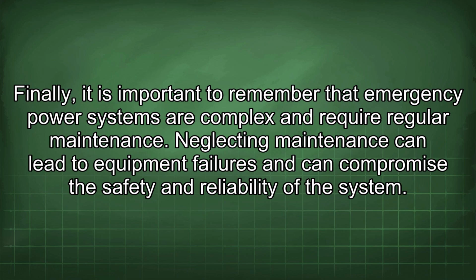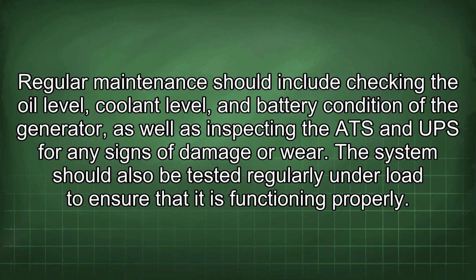Finally, it is important to remember that emergency power systems are complex and require regular maintenance. Neglecting maintenance can lead to equipment failures and can compromise the safety and reliability of the system. Regular maintenance should include checking the oil level, coolant level, and battery condition of the generator, as well as inspecting the ATS and UPS for any signs of damage or wear. The system should also be tested regularly under load to ensure that it is functioning properly.